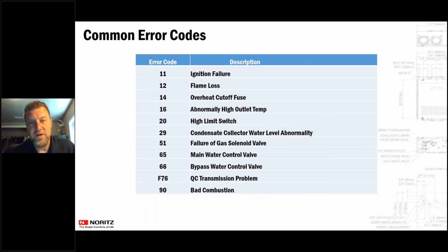We've seen it where they've got 5 inches of water column coming in, they go to light the unit and the water column drops to 2 or 1 or 0, or it just drops. And there's just something wrong with either the meter or the main regulator coming into the house, but that is what a flame loss would be.